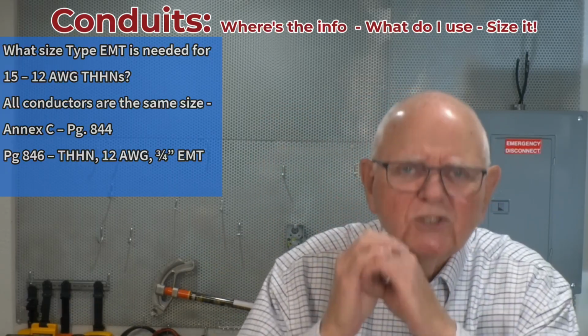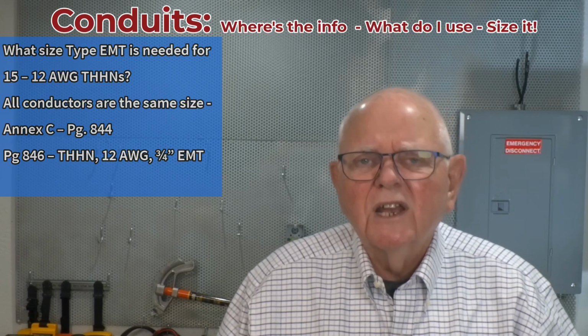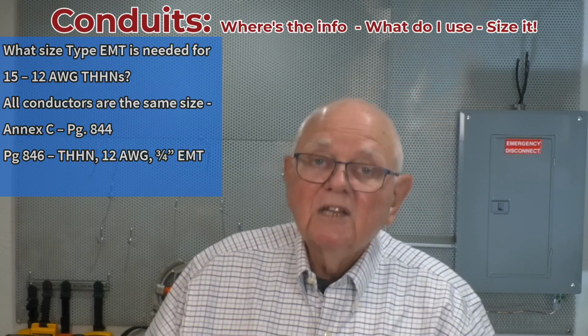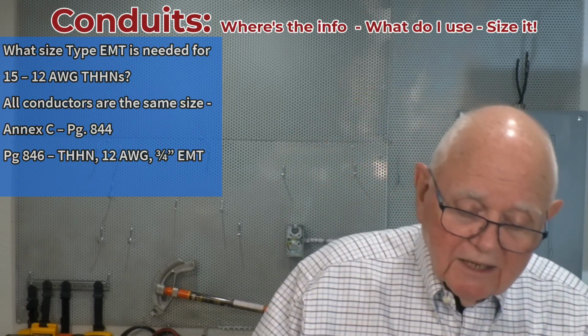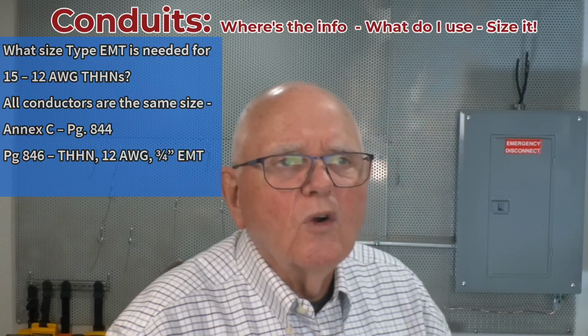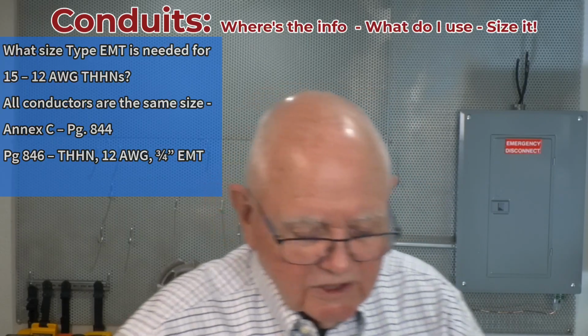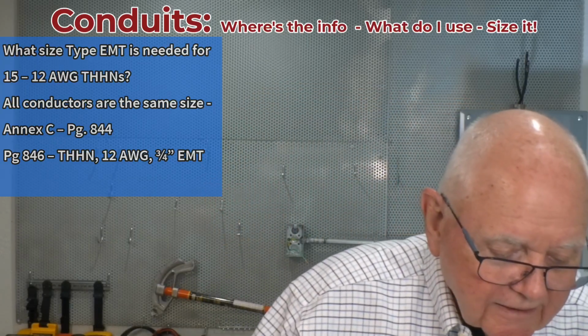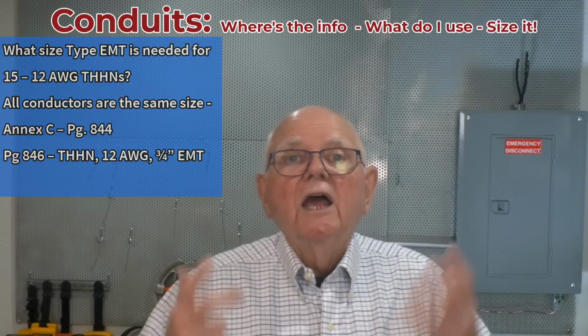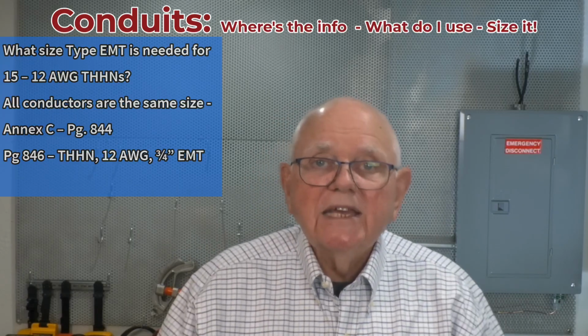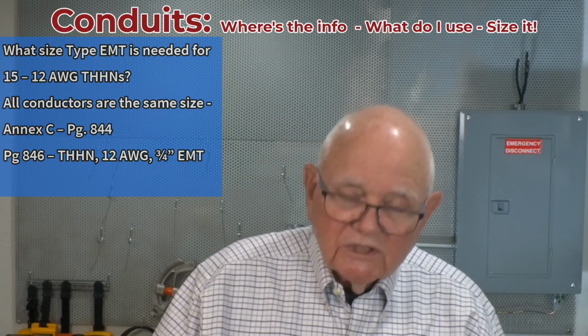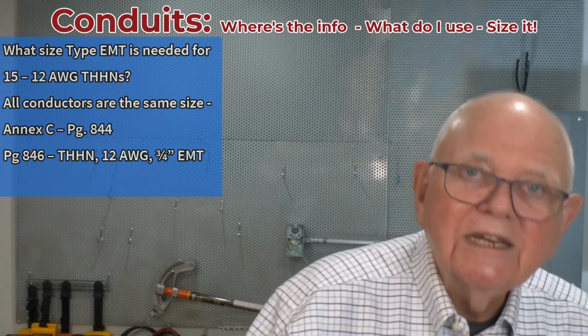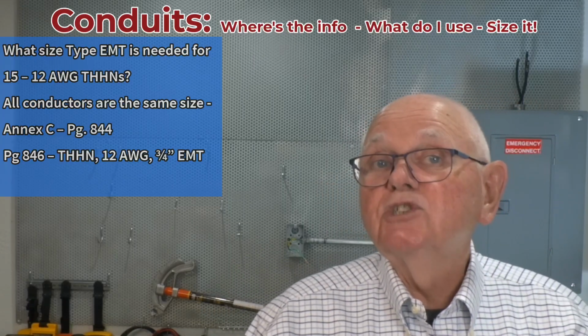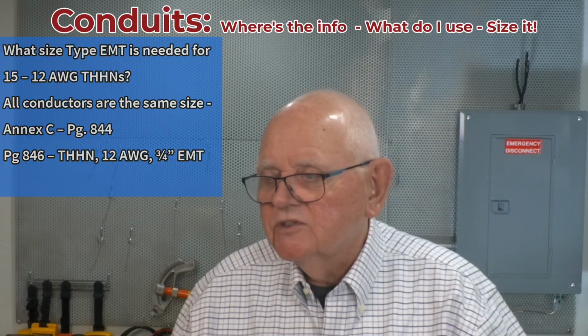Also, dimensions are slightly different for the conductors if I've compact stranded them. So be aware of that difference. Let's take an example. Let's say that I'm going to run some conductors. Maybe I've got 15 number 12 THHNs. What size conduit do I need? EMT conduit, EMT tubing then, electrical metallic tubing.